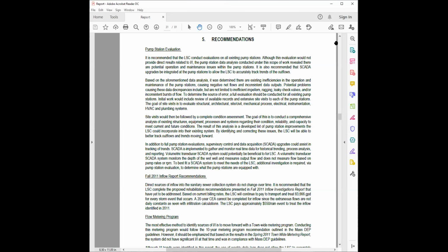What was proposed at that time, in the email string I saw, was that the commission didn't see value in it back then, and maybe now there's more value. It was about $12,000 in 2016 to do an assessment of those stations and look at SCADA capability and communications. You only have one PLC in the system, and it's sort of localized. Your connectivity is by phone line, and your alarming is by landline or leased landline out, dial out to cell phone, which is a communication mode being phased out for these types of systems.